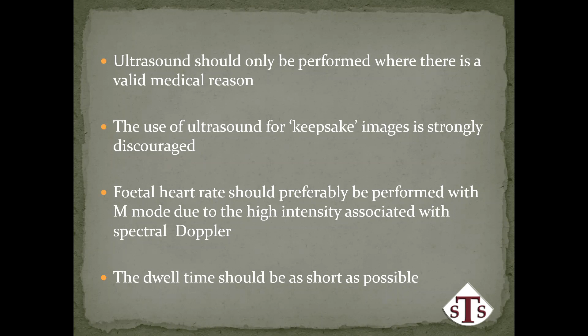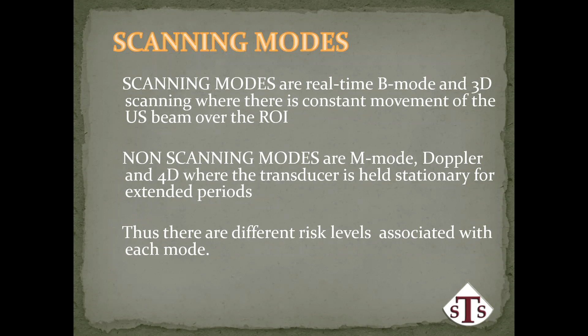Scanning modes have a role to play as well. And this is why when you look at the safety statements, the safe modes are B and 3D scanning. And that is where the sound beam is being moved over different areas of the body constantly. And so you don't have a dwell time of any length. The non-scanning modes are ones with a high dwell time, which is M mode, Doppler, and 4D, where the transducer is being kept stationary in order to achieve the information we need. And so again, the risks are higher with these modalities.